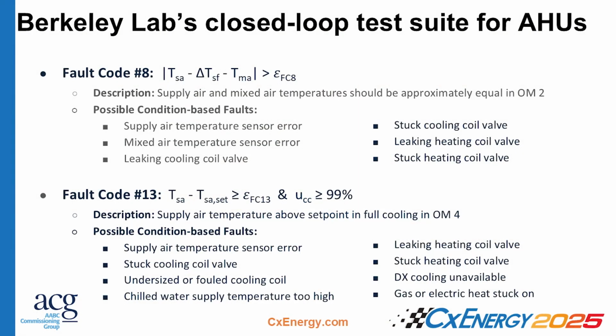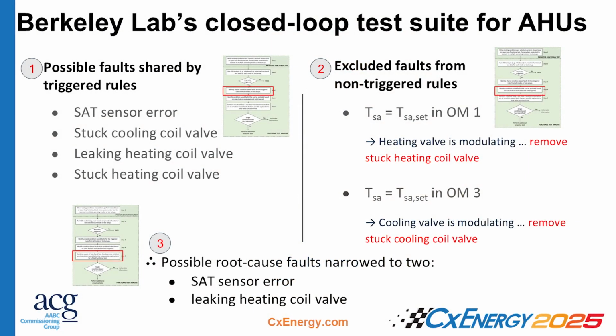So fault code 8 is flagged when supply air and mixed air are not equal when they should be. They should be approximately equal in an operation mode where you don't have any coil valve operation. But in this case, they were different, which means that you have six possible faults that could cause that failed test, right? Running the system through a different mode triggered fault code 13, which is associated with supply air temperature being above its set point in full cooling, right? And that has, you see here, an additional eight faults. But the great thing about running the system in different modes and having these two shared fault codes means that you also have shared faults between them. And the number of possible faults that are associated with both of these is reduced down to two, right?